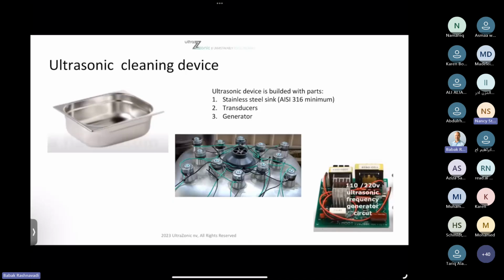Okay, now, how is an ultrasonic cleaning device built up? You have the stainless steel sink, you have the transducers, what you see in the middle. These are the transducers creating the cavitation bubbles, and then you have a generator on the right side. You also have to understand that the more expensive ultrasonic devices sometimes have 3, 4, even 6 generators in one device, just to create all kinds of different frequencies, so that you can choose your program to clean a specific instrument in a specific way. Okay, this is just a basic. This is something that you know.